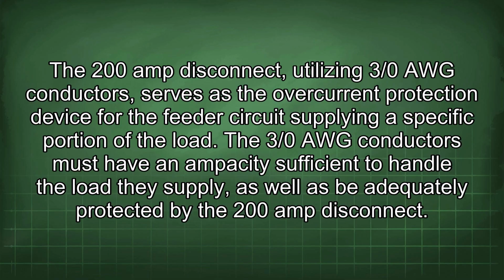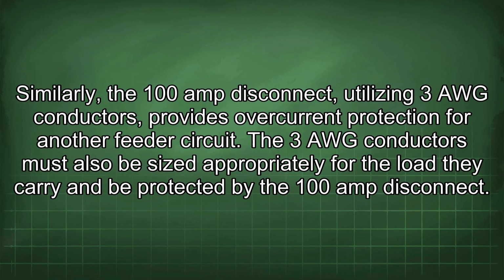The 3/0 AWG conductors must have an ampacity sufficient to handle the load they supply, as well as be adequately protected by the 200 amp disconnect. Similarly, the 100 amp disconnect, utilizing 3 AWG conductors, provides overcurrent protection for another feeder circuit. The 3 AWG conductors must also be sized appropriately for the load they carry and be protected by the 100 amp disconnect.